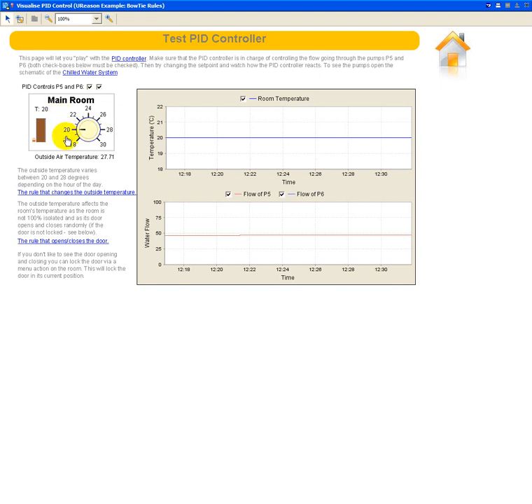If we start playing with the set point here, we'll see the effect on that. So for instance, if I ask for a different temperature, I've asked the system to reduce the temperature inside the room, the PID should react and slowly ask the pump to push a little bit more flow so that the temperature here can decrease from 20 to 19 degrees. So we'll see here slowly the temperature of the room leaving now the 20 degrees and going to 19 degrees. Hopefully it should normally stabilize around that value in a few minutes.